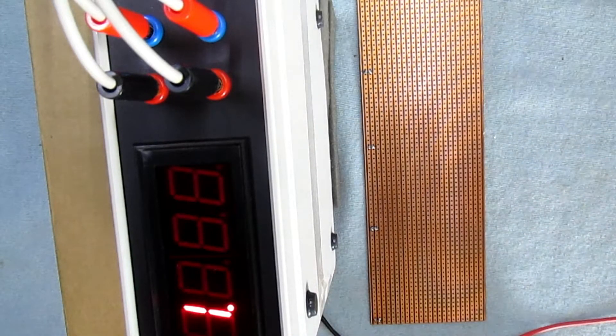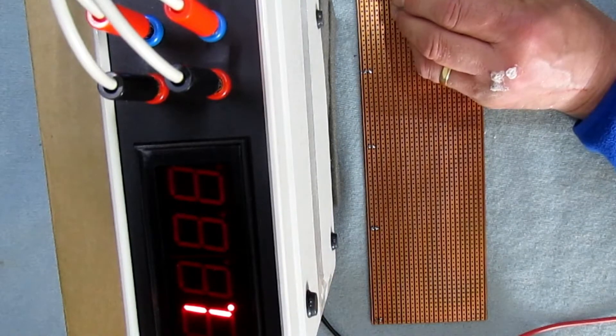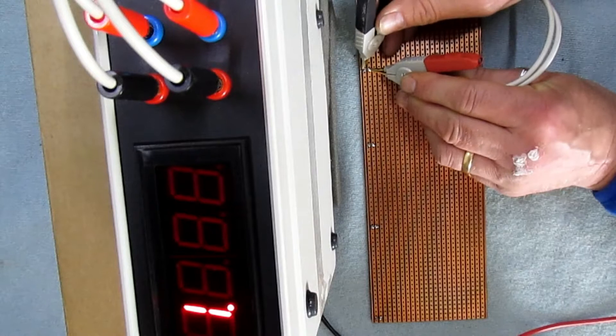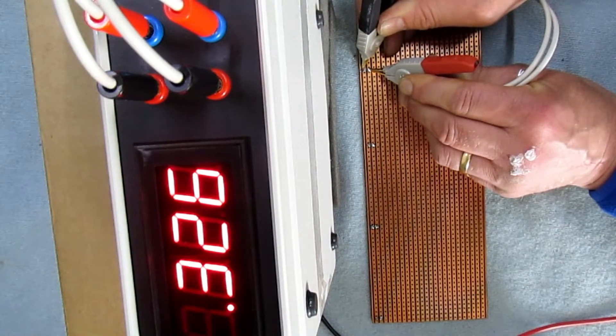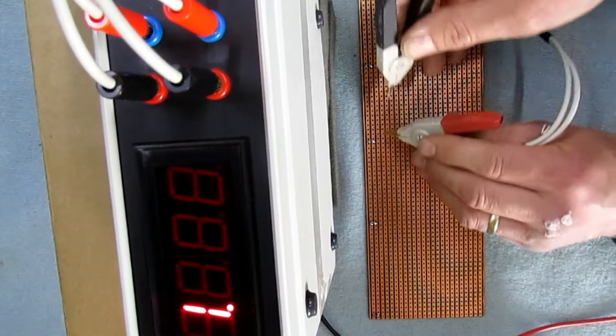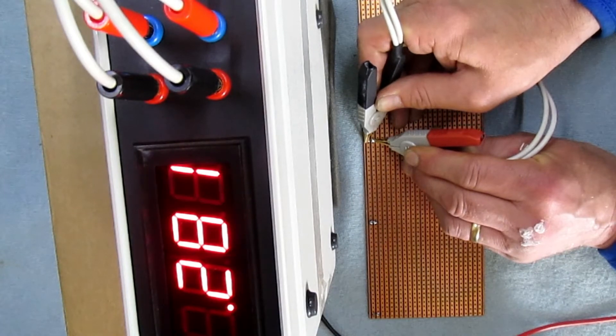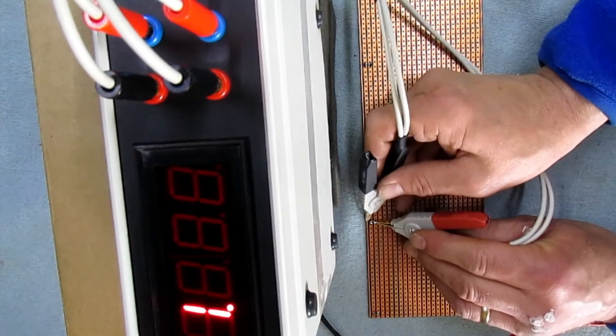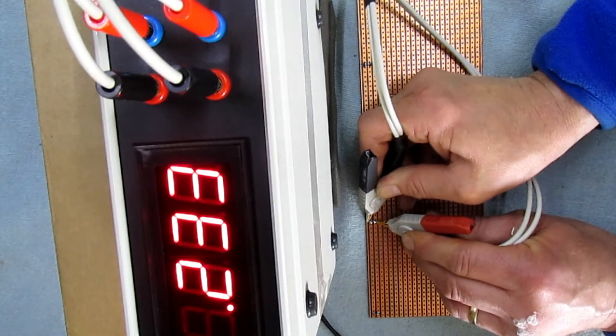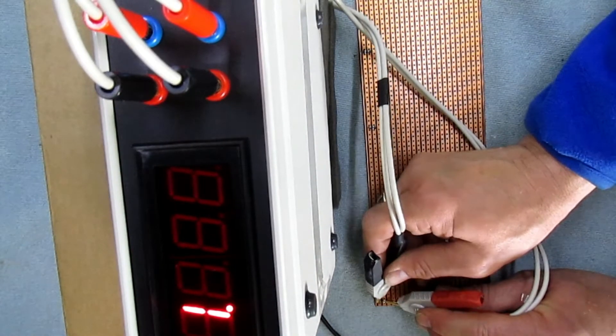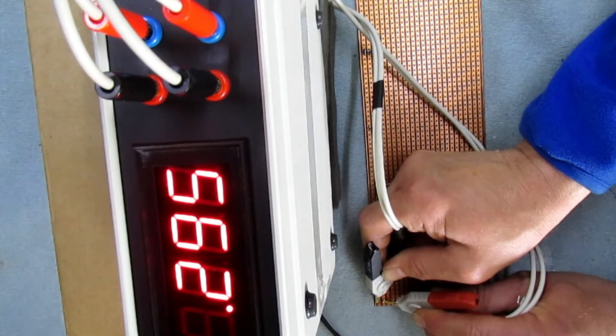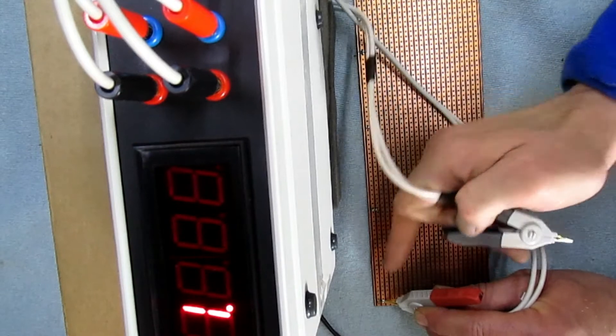Remember, the meter saying that whichever one's faulty, it's more on this side. So we'll start with the one to the other side first. Right, so that's 376 milli-ohms. Now move to the next cap. That's 326 milli-ohms. So you can see the readings falling. And we measure the next one, that's 280 milli-ohms. The next one along again, that's 233 milli-ohms. So the readings still falling.